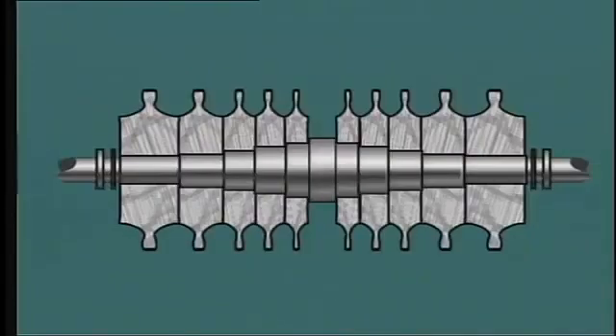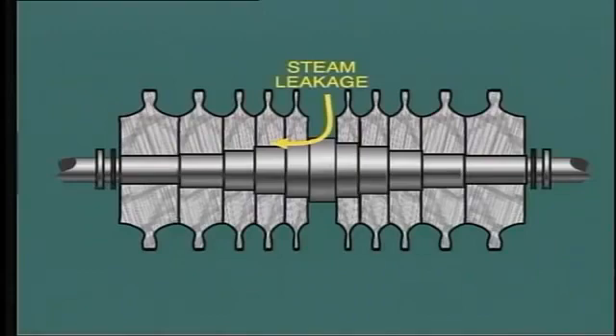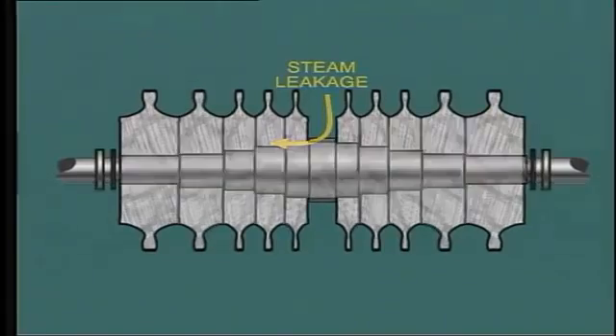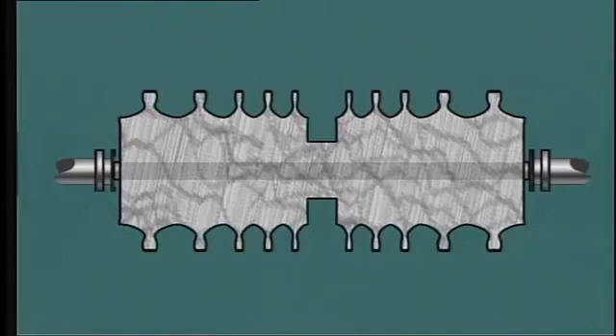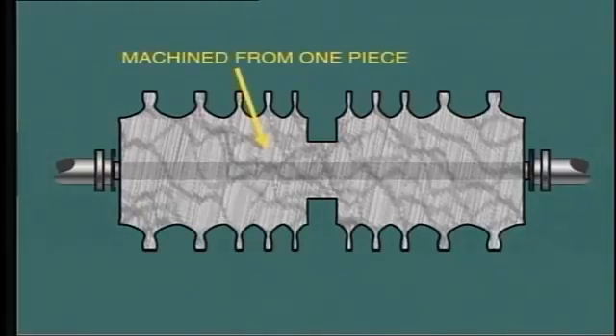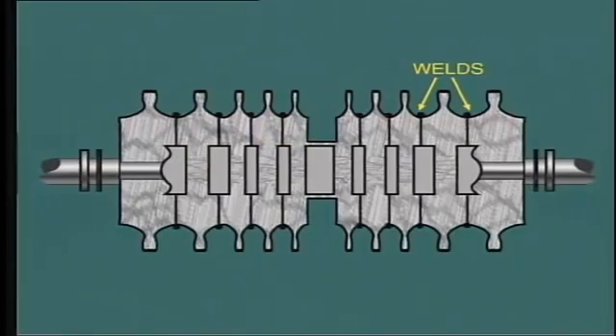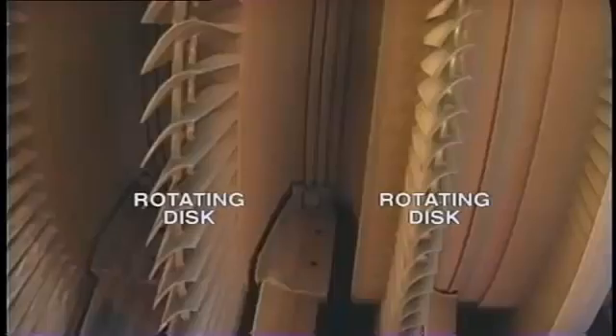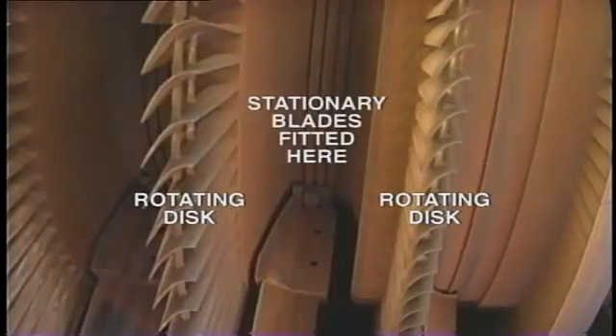In earlier machines, the discs are shrunk onto the rotor shaft. A problem with this type of construction is that in some cases, steam may leak along the shaft and cause distortion due to differential heating as well as a loss of efficiency. To overcome this problem, in modern turbines the discs and the shaft are forged in one piece and then machined. Yet another method of building up the rotor is by welding discs together, eliminating the shaft. In between each disc and associated blades, we have to fit the stationary blades.